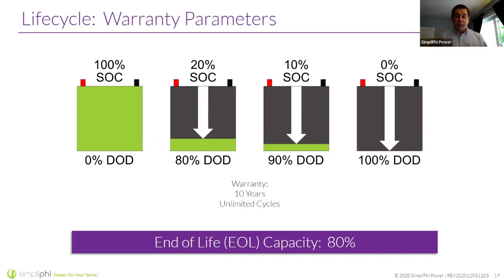We anticipate that if you treat these batteries very, very kindly, you can get a much greater life cycle out of them, more than 10 years. So if you're doing an 80% depth of discharge, you may see many, many more years of capacity. Whereas if you are taking it down to 100% every day, we know that at the end of 10 years you will still have 80% of the nameplate. So whatever it was day one, 80% will remain.